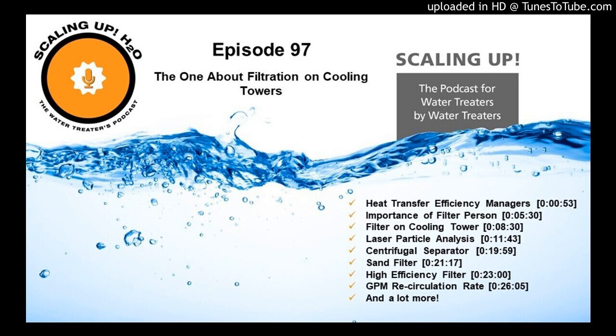Now, where is the best place to install a sand filter on a cooling tower? Our preference is to put it on a recirculation line, generally like you put a stab in downstream and bring that out to the filter, run it through the filter, and put a stab in 6 feet or so downstream from that point. And what that does is it allows the water that comes into the filter and goes out of the filter, the pressure on the filter in and out is the same because it's on a line 6 feet apart.